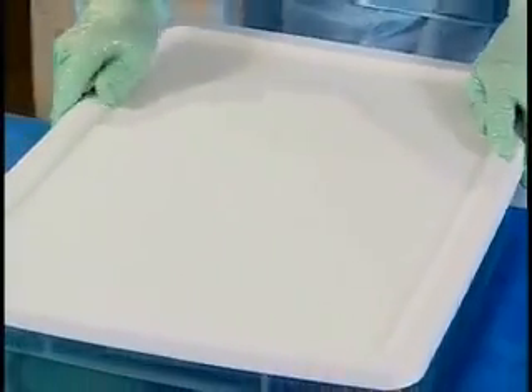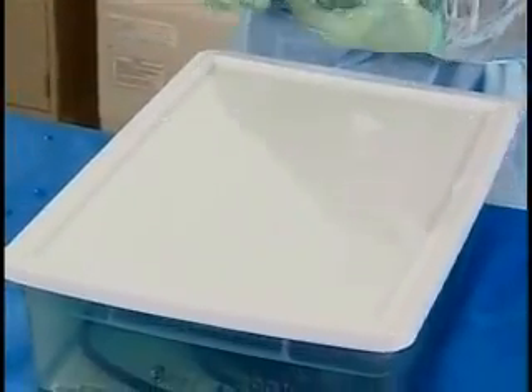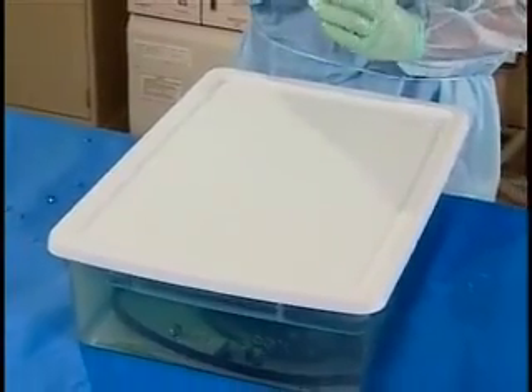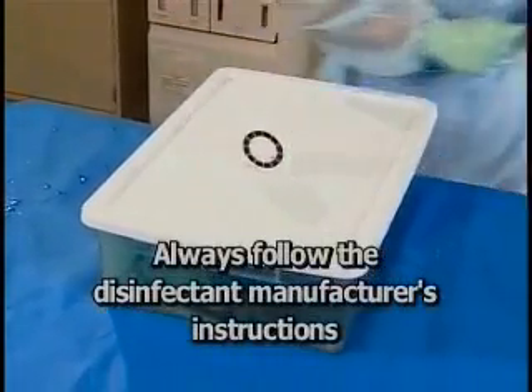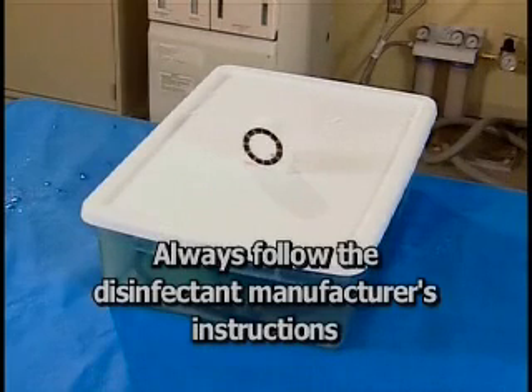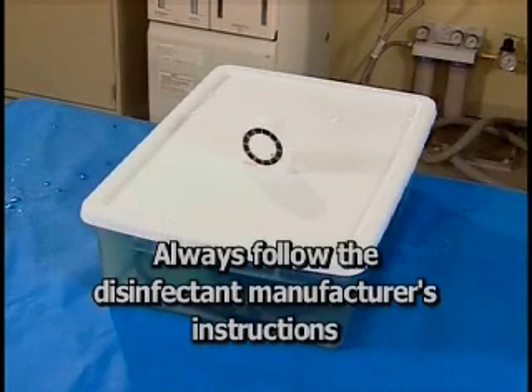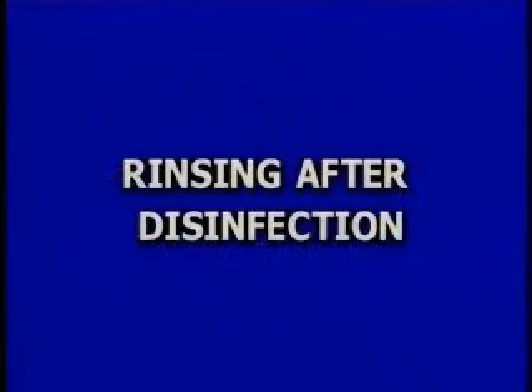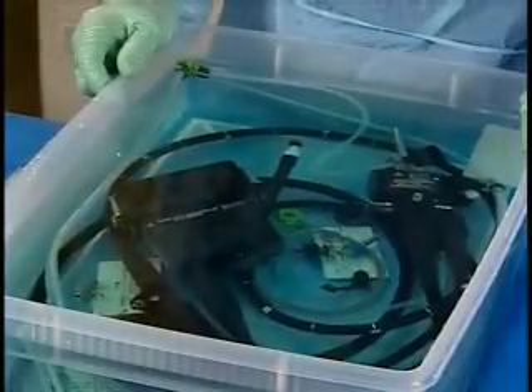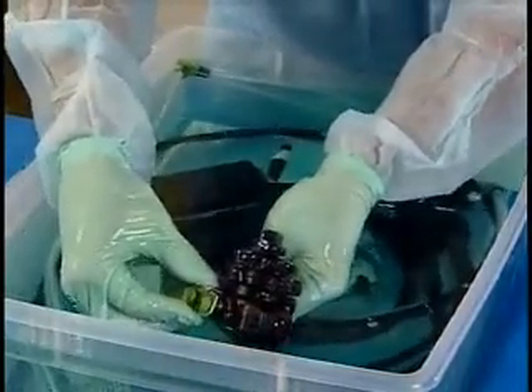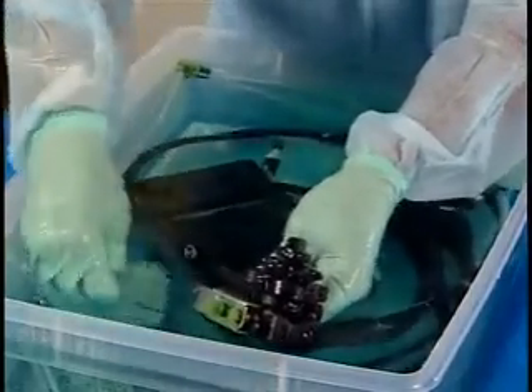Cover the disinfectant basin with a tight-fitting lid in order to contain the disinfectant vapors. Disinfect the endoscope and reprocessing equipment by soaking them in accordance with the disinfectant manufacturer's instructions. Use a timer to confirm that you are achieving the proper contact time. After soaking the equipment in the disinfectant solution for the recommended period of time, reconnect the reprocessing accessories to the endoscope.